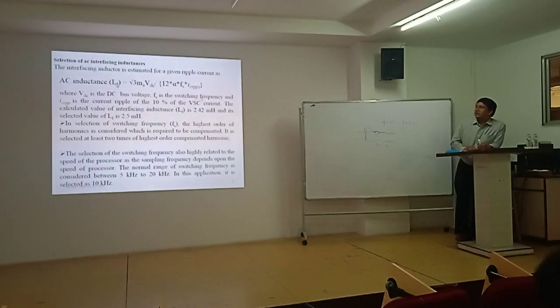Here we are going to take root 3, okay, MA is 1, VDC how much? 700 divided by 12, alpha is 1.2, switching is 10 kHz. Here how much ripple do we want to maintain? 10%. So you can put in all the values, then we can calculate. All the values you can develop based on your system manually. So we are going to have 2.5 mH.